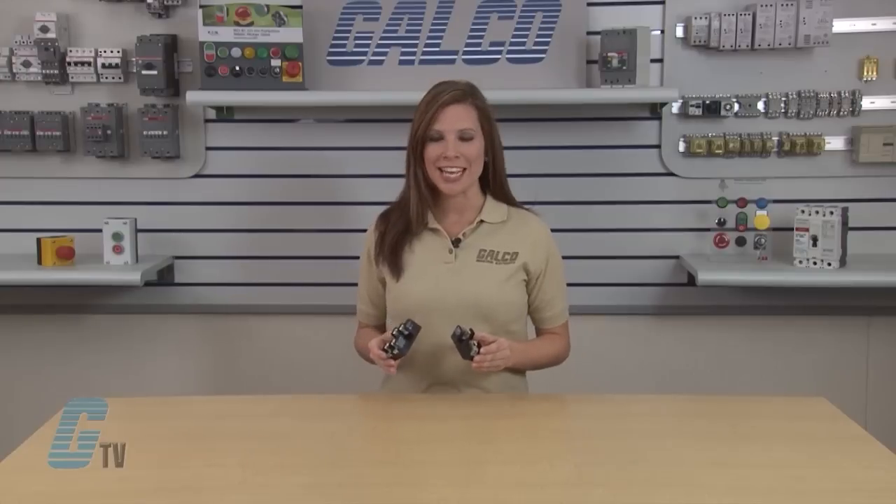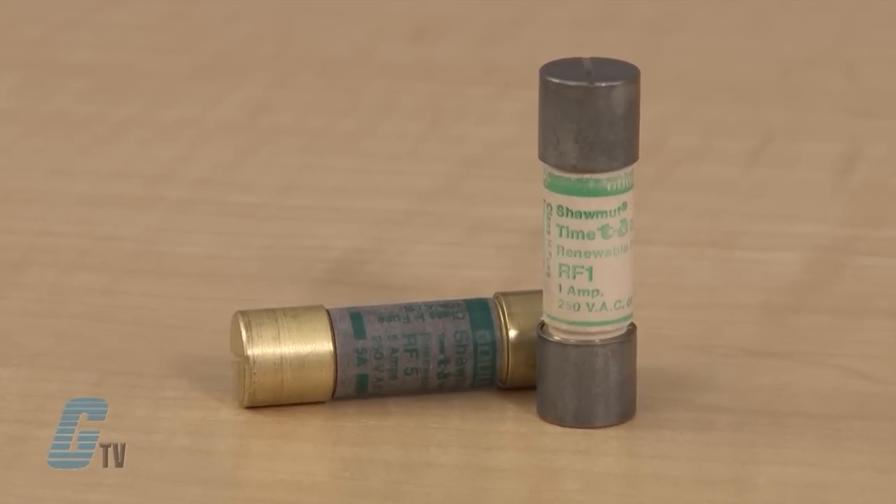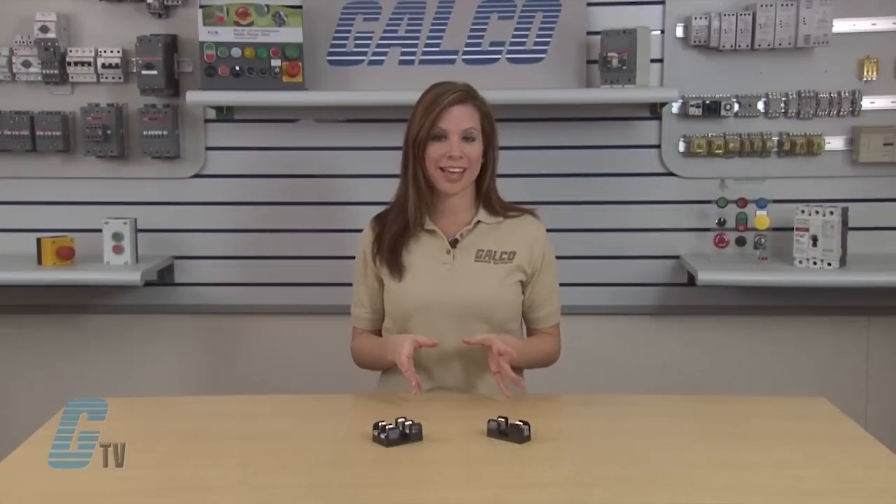Welcome to G-TV. Today I will be showing you Mersen's H&R series of fuse blocks. Mersen, formerly known as Ferraz Shawmut, Class H and R fuse blocks accommodate all Class H&R 250 and 600 volt power fuses. Class H fuses are cartridge fuses intended for general purpose branch circuit, lighting circuit, and the protection of non-inductive equipment like electric ovens and resistance heaters.